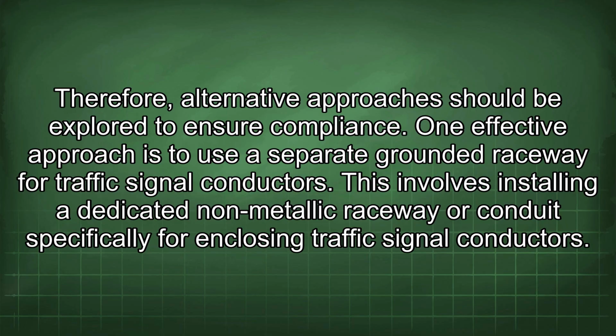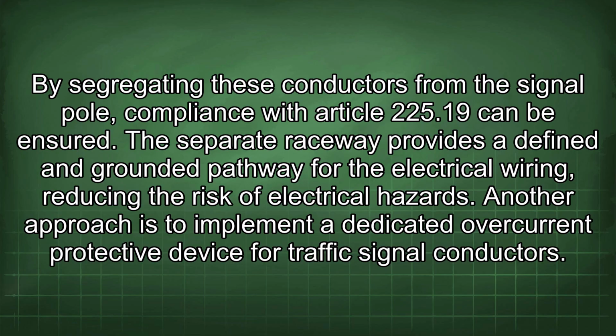One effective approach is to use a separate grounded raceway for traffic signal conductors. This involves installing a dedicated non-metallic raceway or conduit specifically for enclosing traffic signal conductors. By segregating these conductors from the signal pole, compliance with Article 225.19 can be ensured. The separate raceway provides a defined and grounded pathway for the electrical wiring, reducing the risk of electrical hazards.